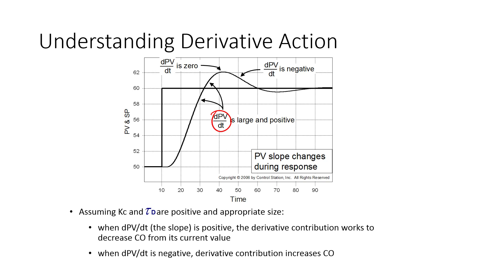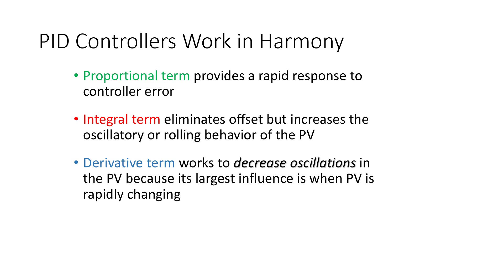Relating back to the PV, d(PV)/dt is zero at steady state, becomes a very large positive value as the PV rises, then zero again at the peak, and negative as it falls. You just visualize the slope of that signal — that gets included in your PID equation. To summarize: the proportional term provides rapid response to control error; the integral term eliminates offset but increases oscillatory behavior; and the derivative term works to decrease oscillation, slowing response when approaching a set point too fast.